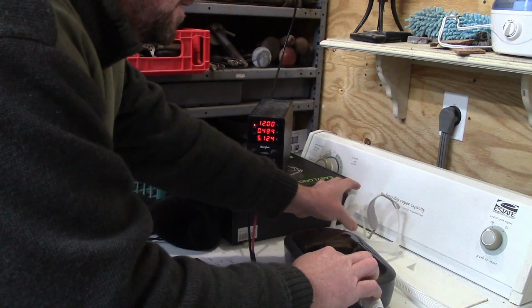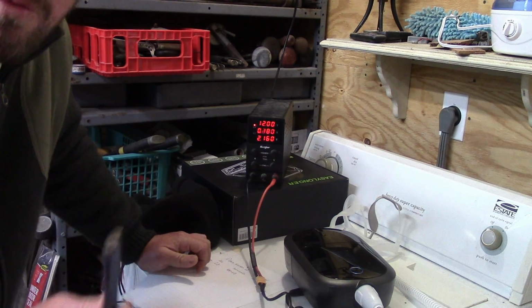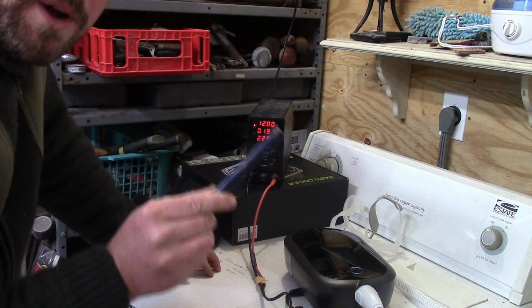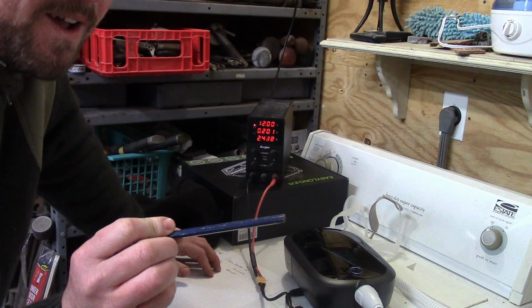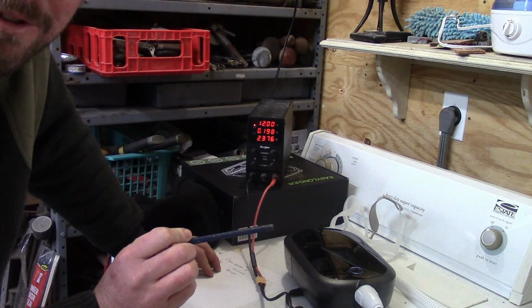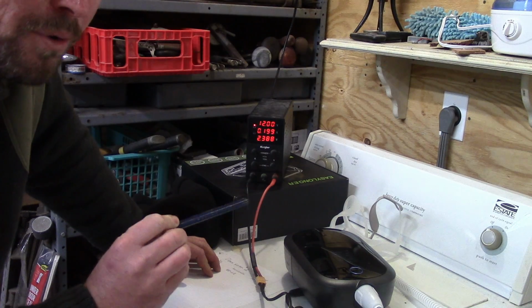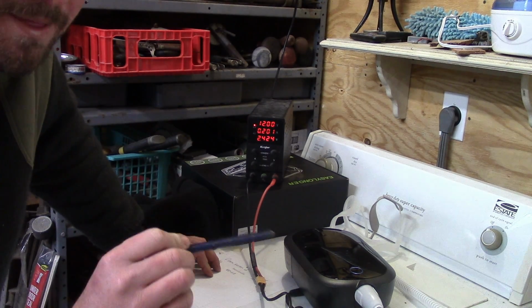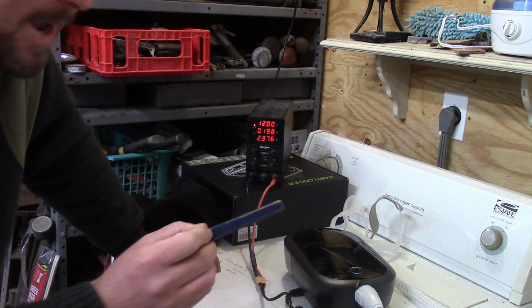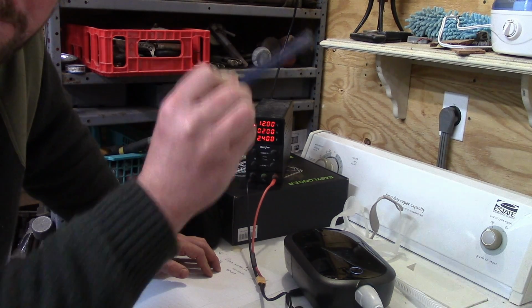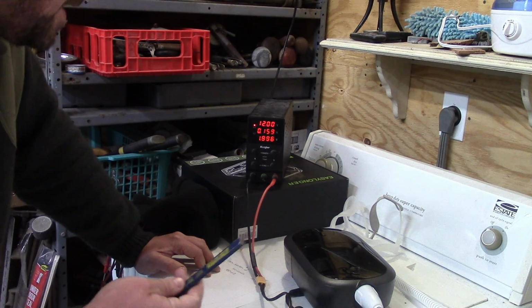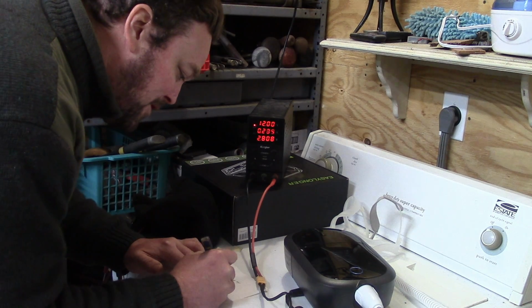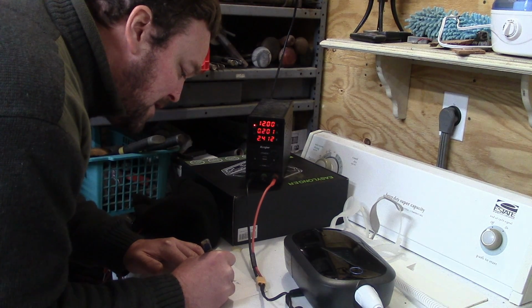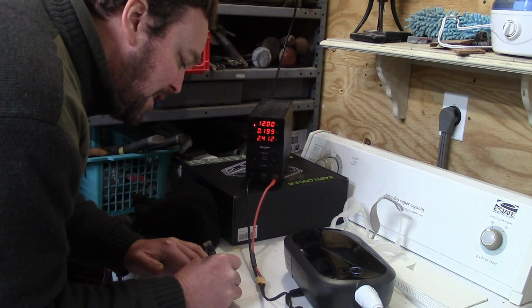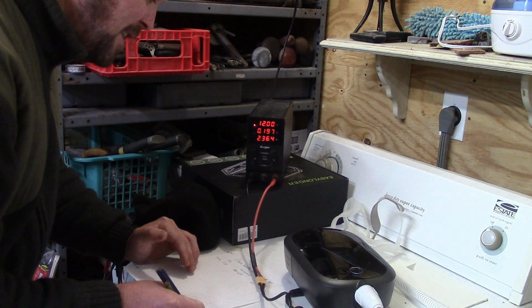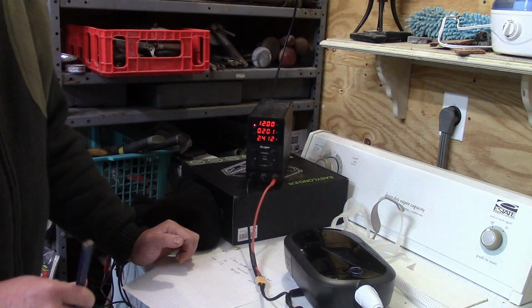Okay, so with heat and humidity turned off, what that looked like to me was during exhalation, it would go down to about 2.5 watts, and breathing in, steady, normal breath in, would go up to about 10 watts. I did do one sharp breath, and it popped up to 45 watts, but let's just say for no heat and humidity, this device uses between 2.5 watts and 10 watts. And we'll take the mean of that for our calculation too.